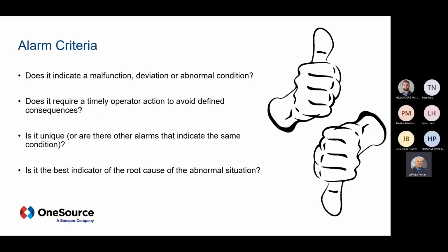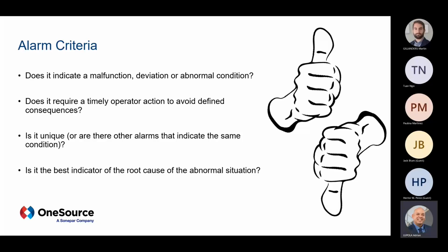And the last is: is it the best indicator of the root cause for that abnormal situation that you're dealing with? So once again, all of these should be looked at as criteria before you actually set this alarm situation within your HMI.